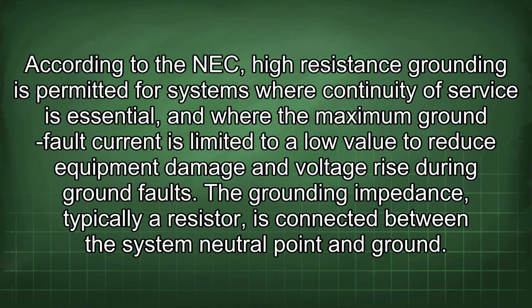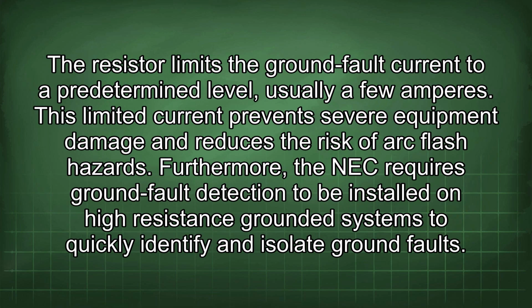The grounding impedance, typically a resistor, is connected between the system neutral point and ground. The resistor limits the ground fault current to a predetermined level, usually a few amperes. This limited current prevents severe equipment damage and reduces the risk of arc flash hazards.